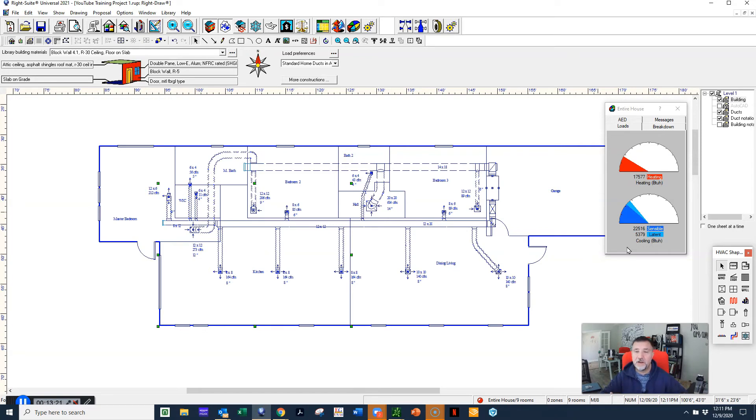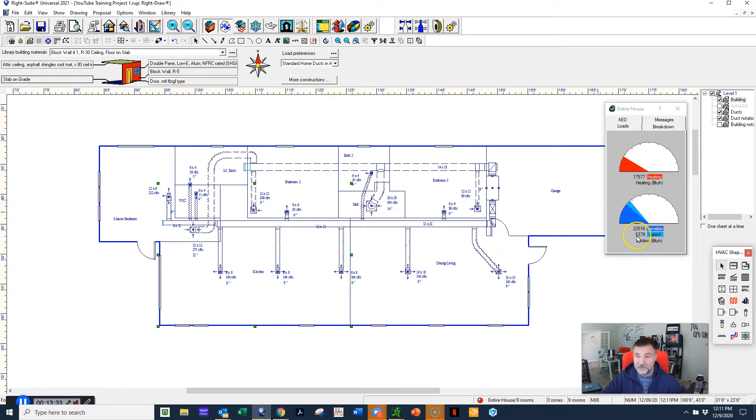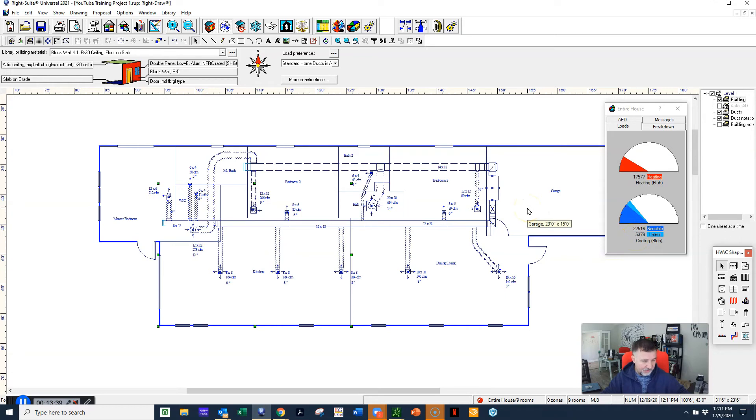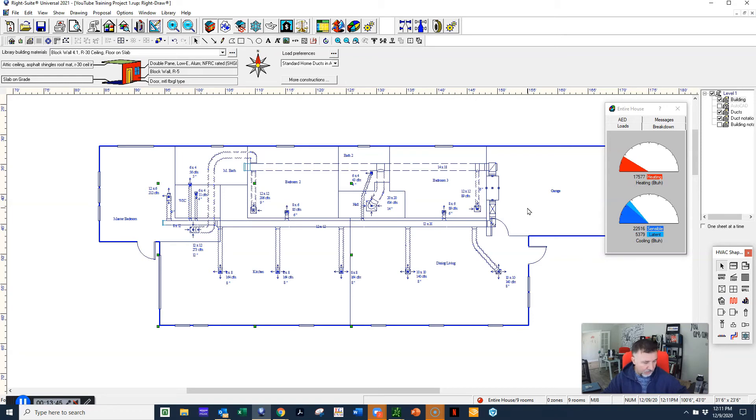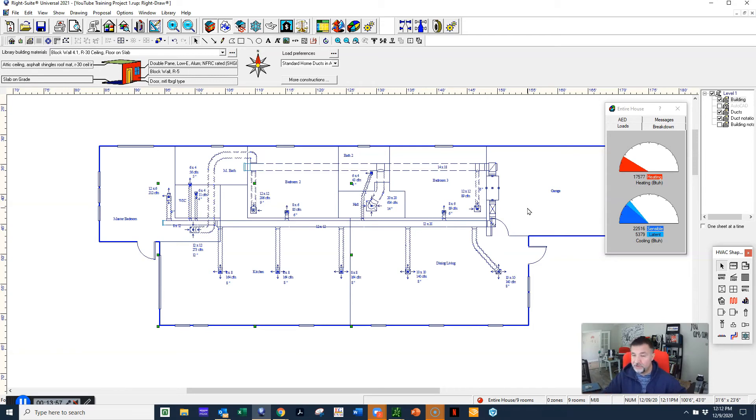This is just to give you a better bird's-eye understanding of how much truly goes into getting the right loads so that you're not using that 400 to 500 square foot per ton. Right now this house is at 27-28,000 BTUs and this is a 1,900 square foot house, so that's under two-and-a-half tons, right around two-and-a-half tons. So 1,900 divided by 2.5, that's 760 square foot per ton—nowhere near 400 to 500—and we're not even using super high efficiency insulation and windows and stuff in this.